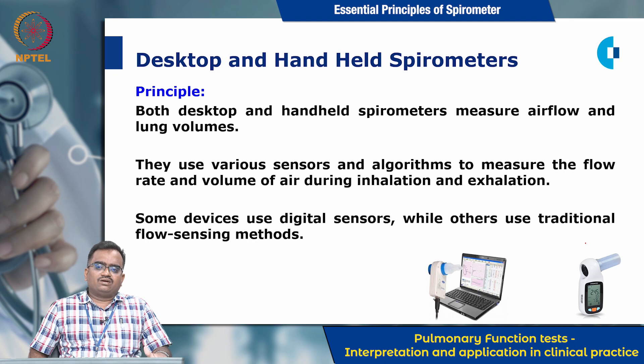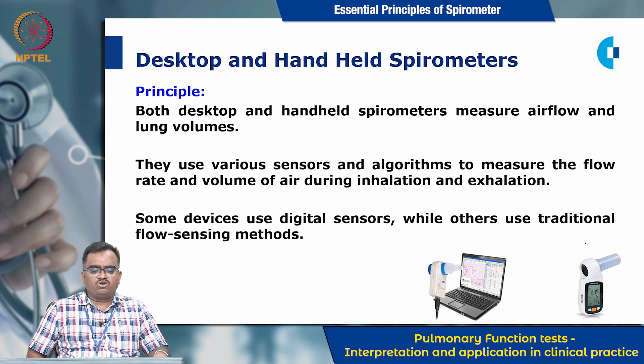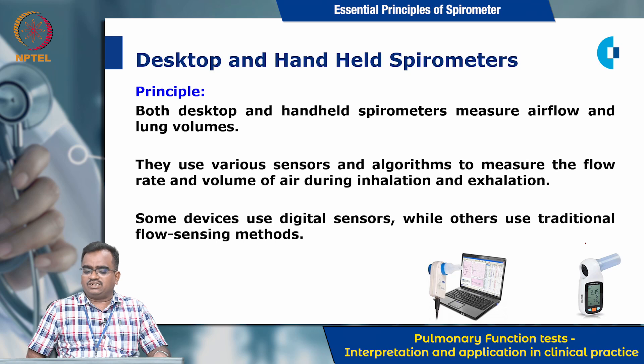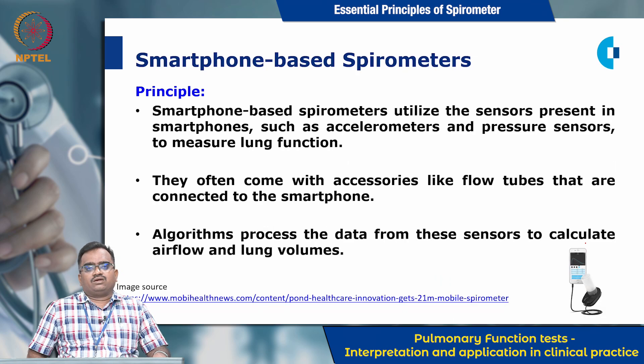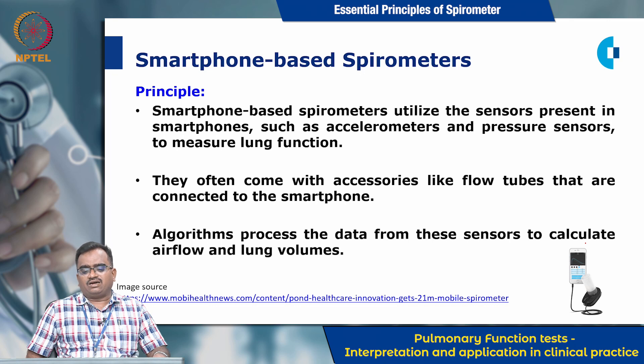The commonly used spirometers are desktop and handheld spirometers and smartphone-based spirometers. Both desktop and handheld spirometers measure airflow and lung volumes, using various sensors and algorithms to measure the rate and volume of air during inhalation and exhalation. Smartphone-based spirometers utilize sensors present in smartphones such as accelerometers and pressure sensors to measure lung function, often with accessories like flow tubes connected to the smartphone. Algorithms process the data from these sensors to calculate airflow and lung volumes.